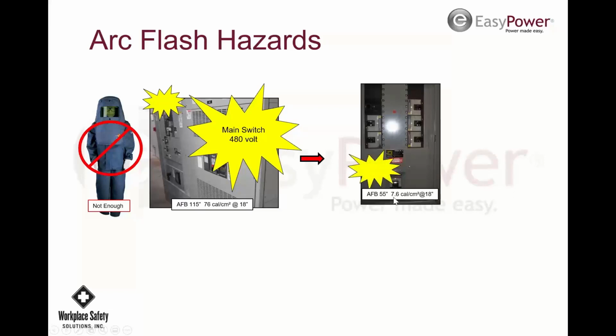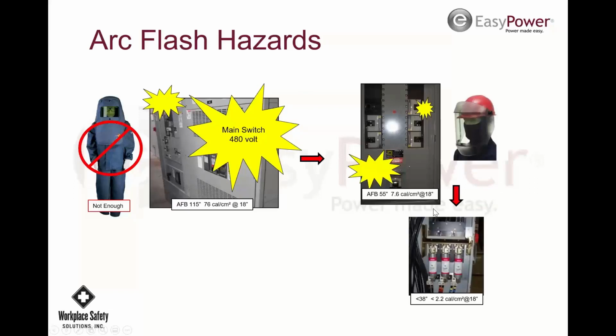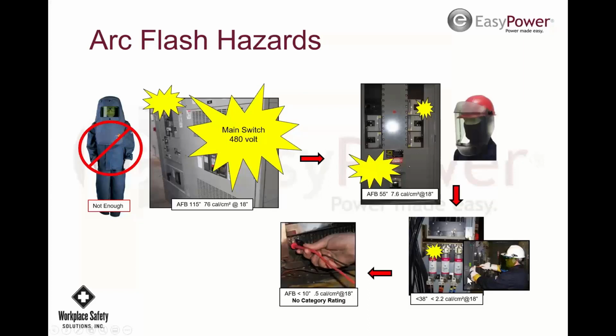55 inches arc flash boundary on the panel, 7.6 calories. So they're going to wear a shield and a balaclava. Downstream from the breaker, we're going to a disconnect switch. We're down to 2.2 calories, still over 1.2. So we're going to wear a shield and arc-rated clothing. Rubber gloves with leather protectors, by the way, are now also not just shock protection, but also arc flash protection. So now we're down to 0.5 calories.